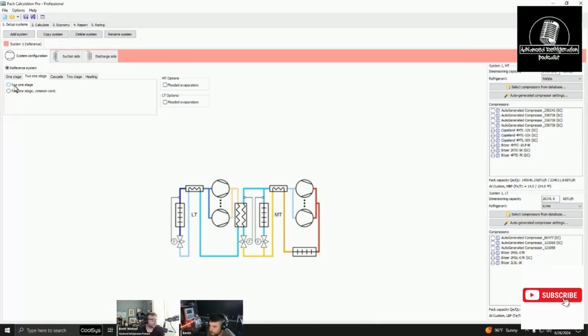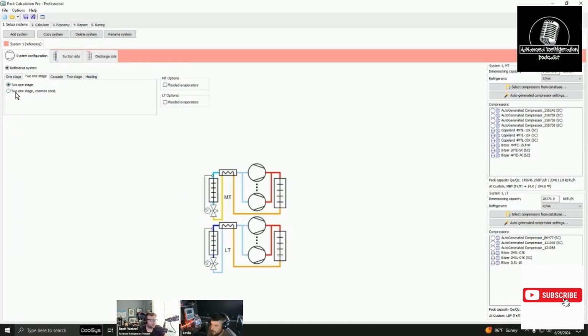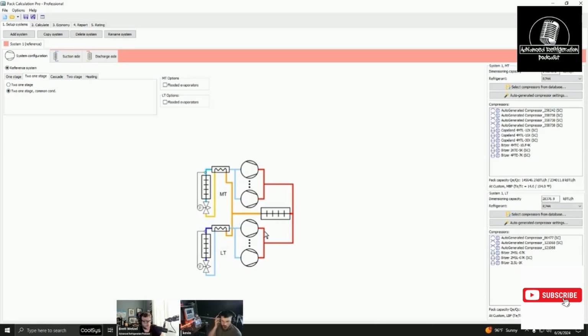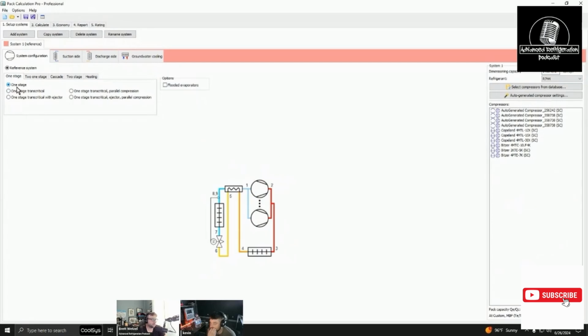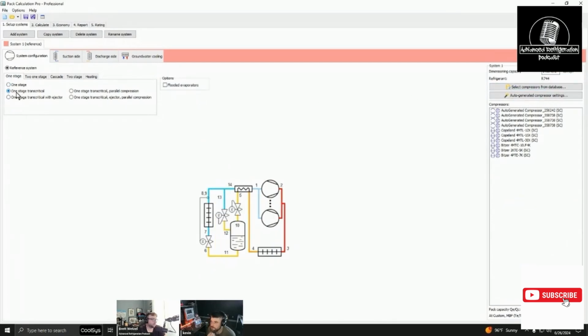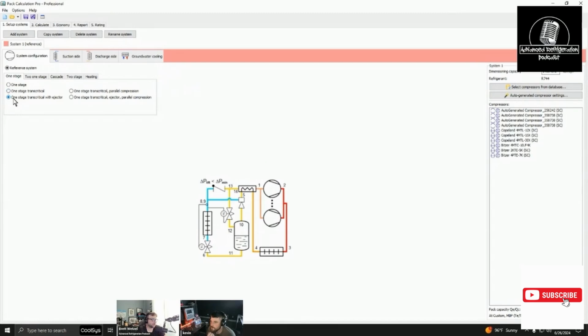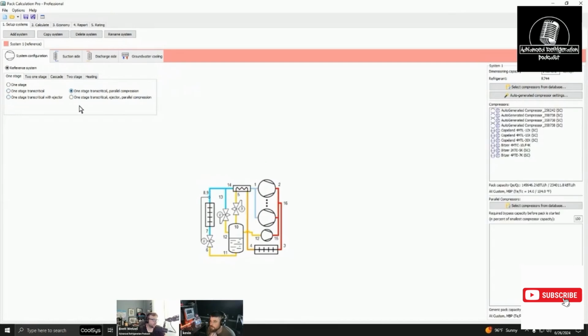Yeah, all right. So anyway, you have 1-stage and 2-stage common condenser, basically a regular standard HFC booster. I guess you could make it CO2 as long as some of them are running critical. Then you have 1-stage, which is just a regular standard system - 1-stage transcritical, 1-stage transcritical with ejectors, 1-stage transcritical with parallel compression.